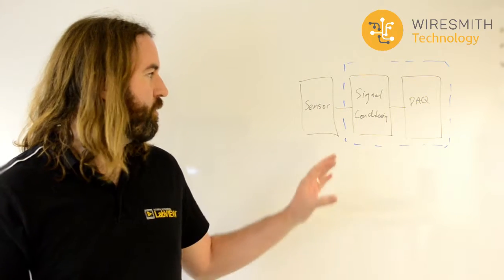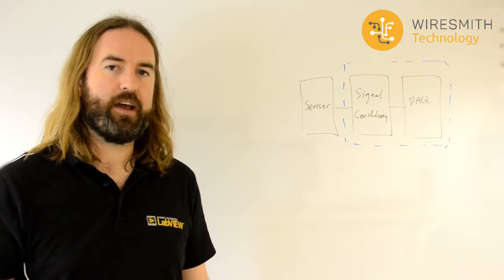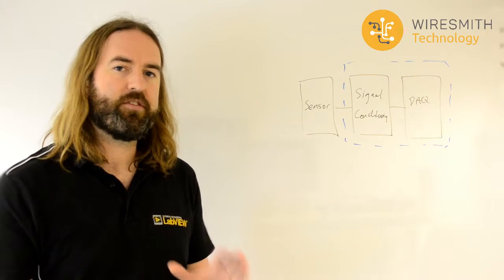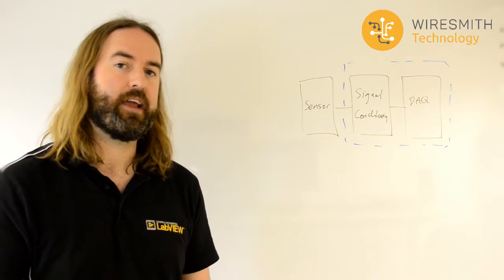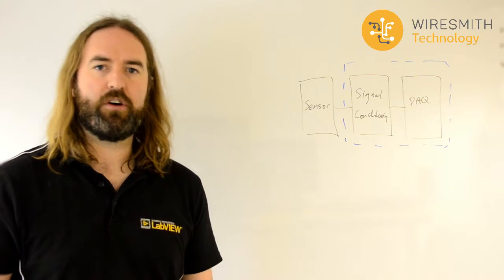And if the individual components drift too far out of calibration, even if you're doing system calibration, what can happen is they can start to introduce some non-linear elements which your calibration won't take account of. So there's still some benefit to having these items individually calibrated periodically as well. But it certainly goes a long way to build trust and give you some control over how you look after your systems.